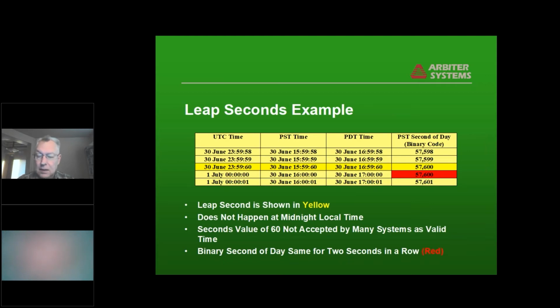At the least, a lot of systems have what they call an error bypass, so that when the time changes, it looks for a consistent time change that lasts for several seconds. The purpose of that is to ignore a transient error. What that'll mean if that happens and a leap second occurs is it'll be 3 or 4 seconds after the top of the hour when the clock and the IED finally says, well, I guess the time really did change. And that's where the problems with leap seconds come from.